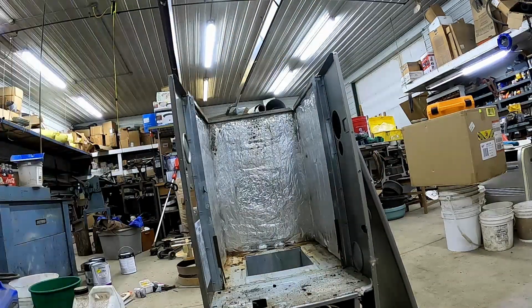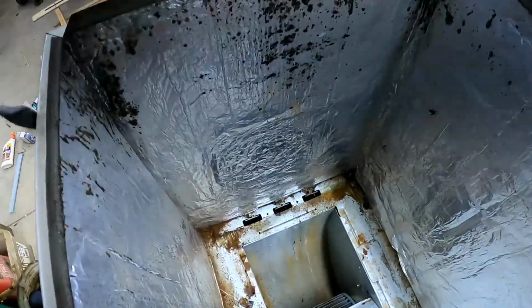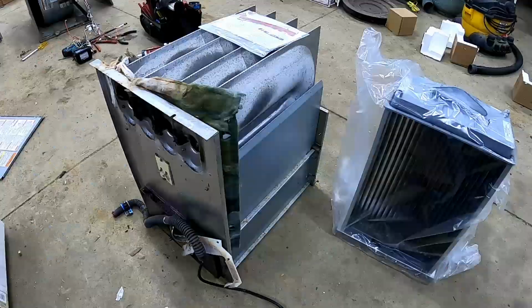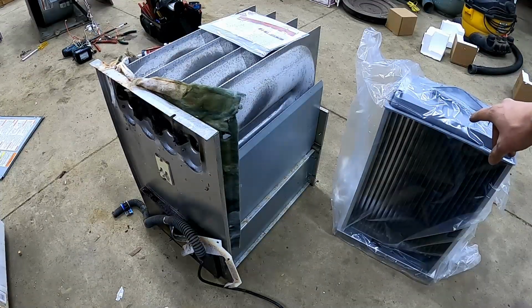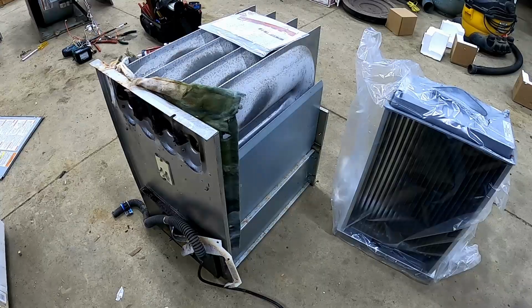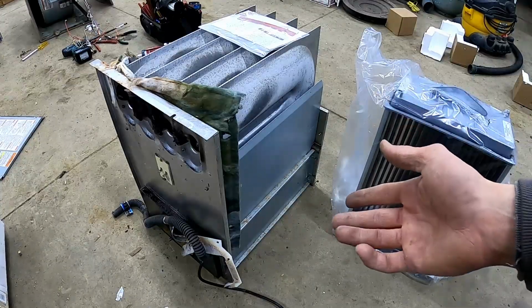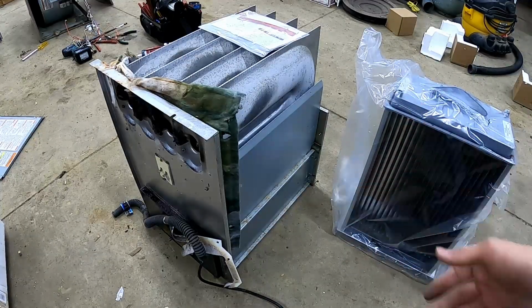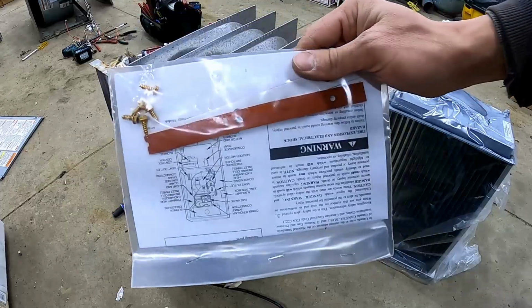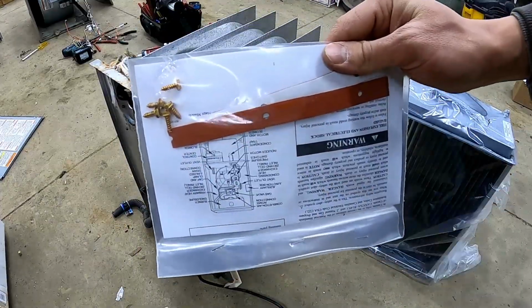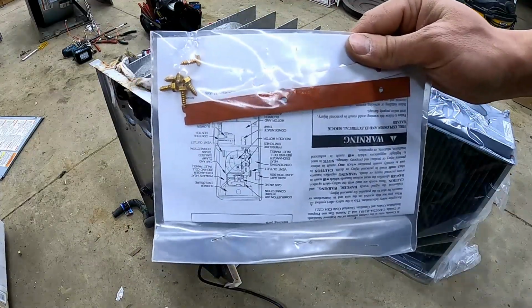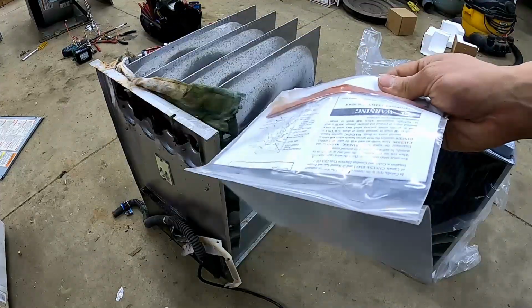So that's what we have when the furnace doesn't have the heat exchanger in it, just the blower. So you can see that the plastic is gray on this one and it's black on that one. They do that usually so that you don't accidentally put a second heat exchanger into a furnace that's already had one replaced. It should also come with this seal and some new screws that go in where the baffle is, because they are usually in really tough shape.